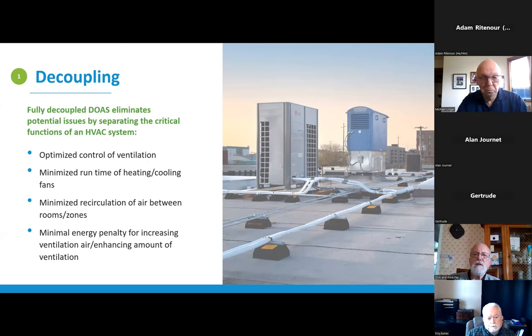So that first key component is a fully decoupled ventilation and heating and cooling system. This approach allows both systems to be controlled and optimized independently. So that means that the ventilation system can be scheduled and controlled for occupancy. So it provides flexibility in that way. And on the other hand, the heating and cooling system delivers comfort conditioning and controls the temperature of the different indoor zones without regard to the ventilation system. And in this way, each one of those systems can provide the critical function that they're intended to.